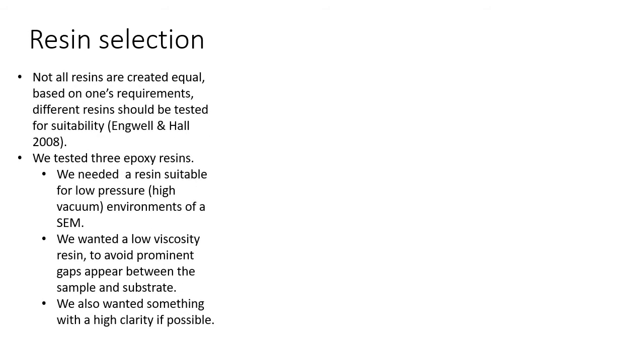Once you have decided whether you want to have a resin block or a thin section, it now comes down to your selection of resin. Not all resins are the same. There were three main criteria that we wanted to select for our resin. We needed a resin that was suitable for low pressure environments, like in an SEM, because some resins can actually give off residual gases which can contaminate the internals of your SEM.